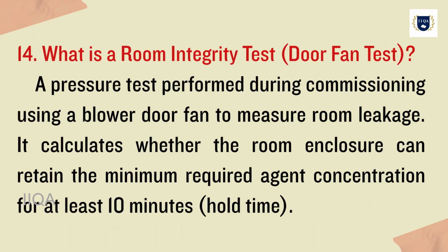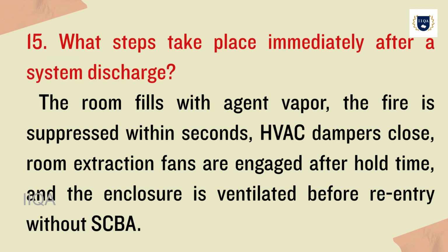14. What is a room integrity test, door fan test? A pressure test performed during commissioning using a blower door fan to measure room leakage. It calculates whether the room enclosure can retain the minimum required agent concentration for at least 10 minutes, the hold time.